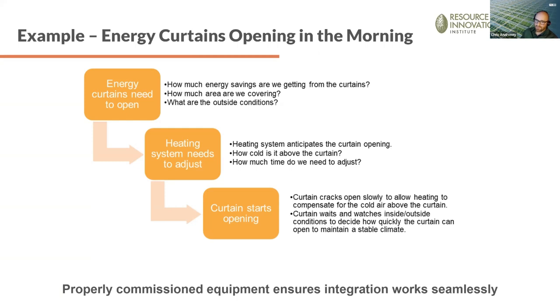We need to know how cold it is above that curtain and how much time we need to adjust. So we need to make sure that we have all the proper information as far as energy savings goes. We need to make sure that all our sensors are reading properly so that the greenhouse control can react accordingly. And we need to make sure all of those pieces of equipment are working properly as well. Are the curtains working properly? Are the curtain position sensors calibrated so we know exactly where the curtains are at any given time? Also, if we don't have curtain position sensors, are the proper run times put in if we're running the curtains on time? Is that mixing valve working properly? So when we turn on the heat to offset the temperature in the air, do those mixing valves open properly? Is the sensor reading properly?